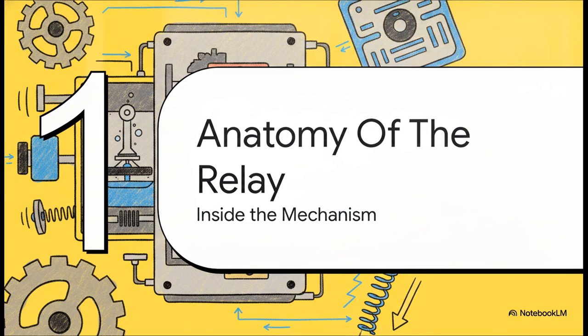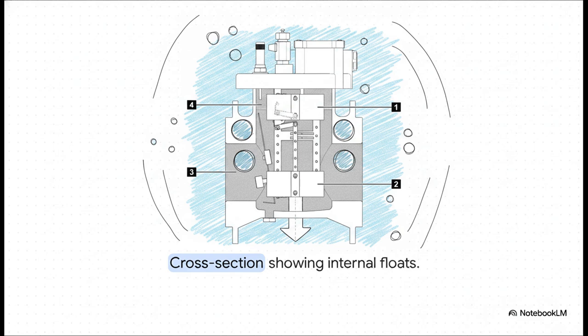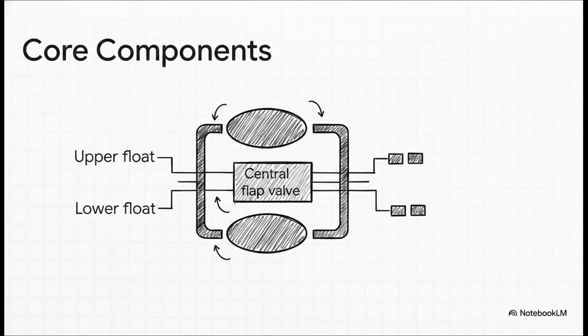Section 1. Anatomy of the relay. Inside the mechanism. Let's peek inside the chamber. Floating in that insulating fluid, you'll find three totally vital mechanical parts. Notice the upper float gauge pair near the very top. Directly beneath that is the lower float gauge pair, and right there, hanging in the main fluid pathway, is the flap valve.